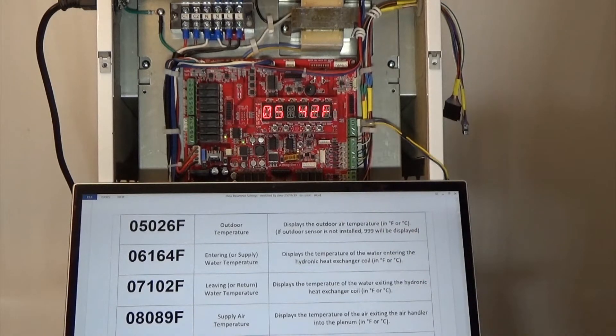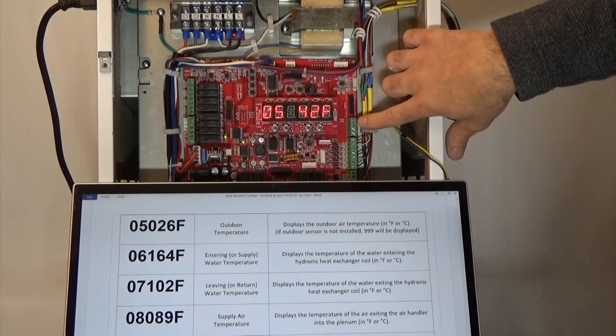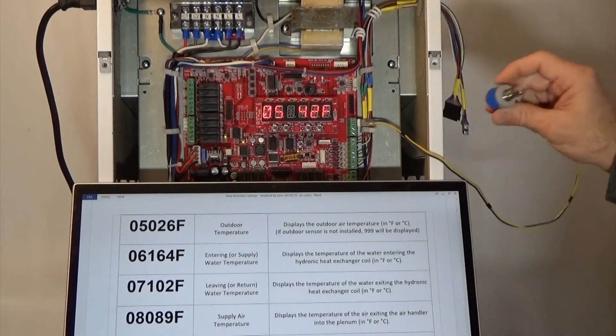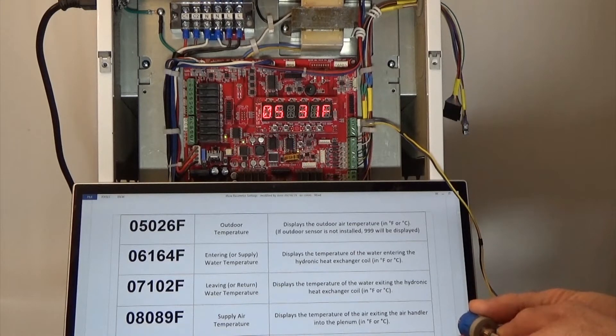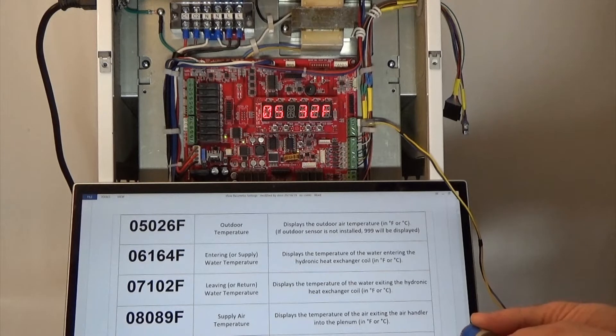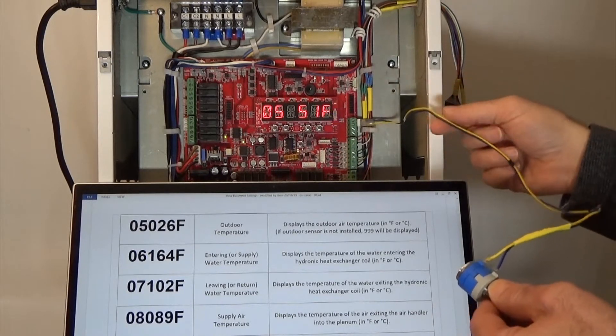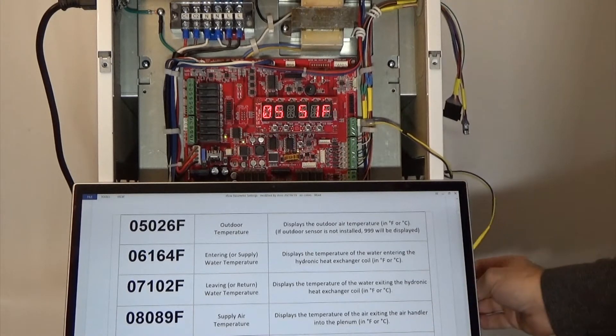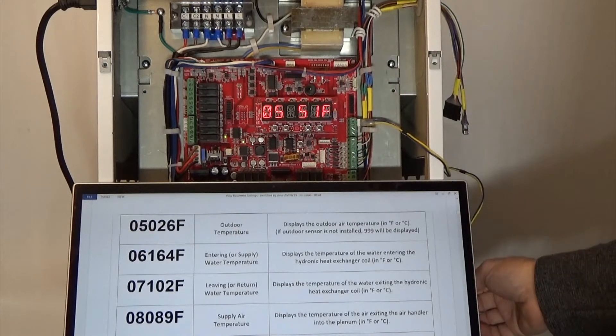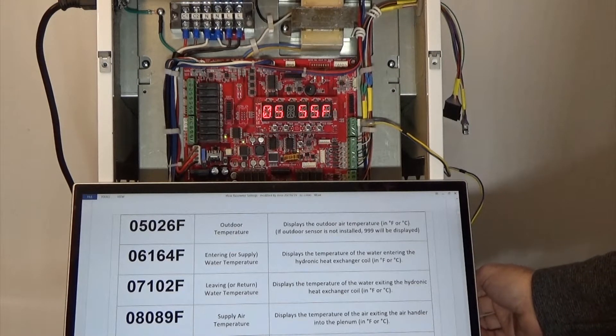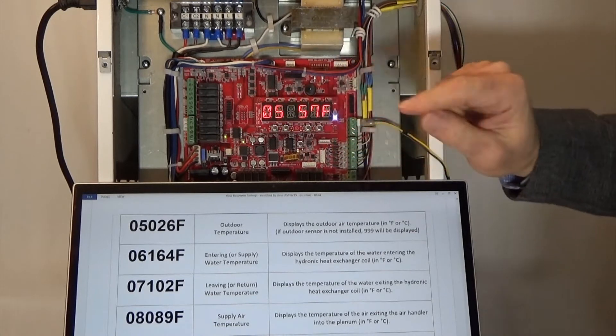Parameter number five is the outdoor temperature sensor. We have the outdoor temperature sensor wired into the board at this location, just to the right. We have a potentiometer that will simulate the outdoor temperature, so we can actually adjust it down or up as needed. When you're in the field with this installed, the actual sensor would be run outside, seeing the real outdoor temperature. The potentiometer is being manipulated here for demonstration purposes only.